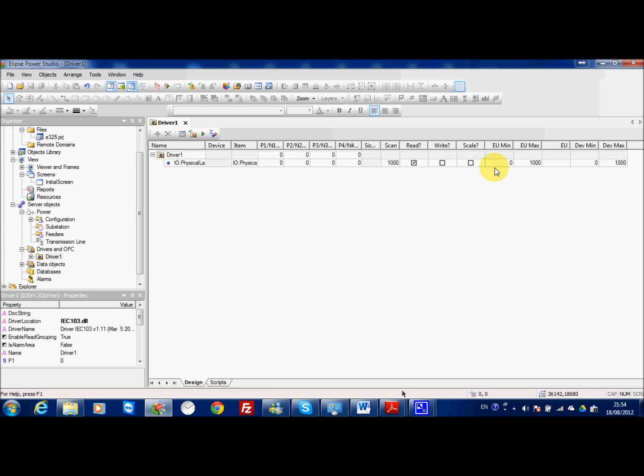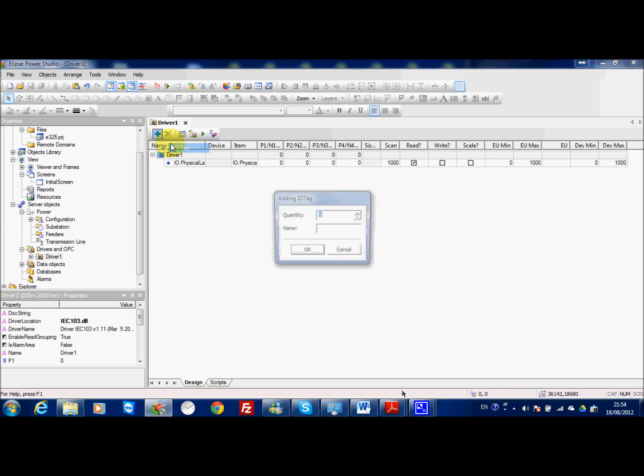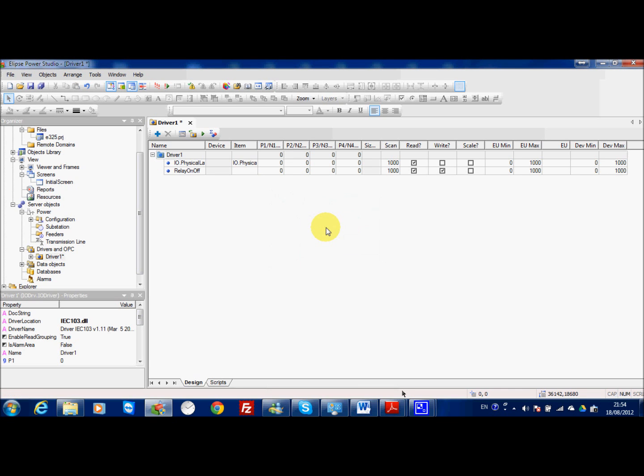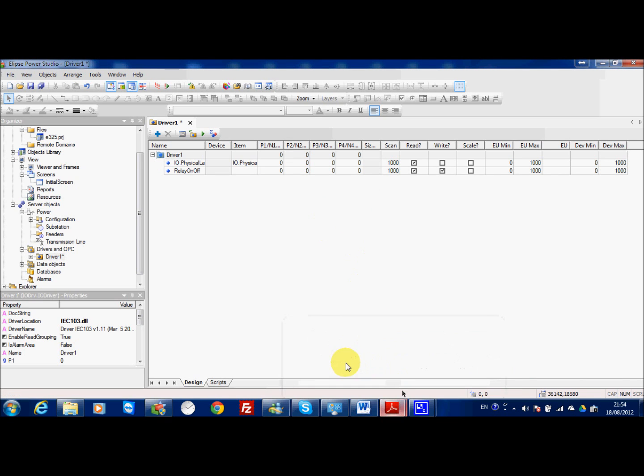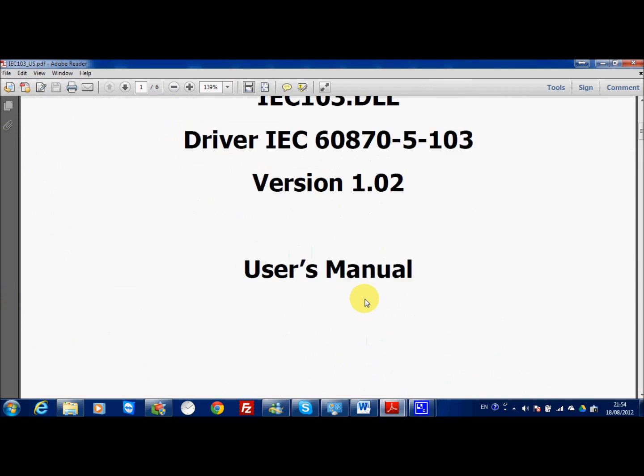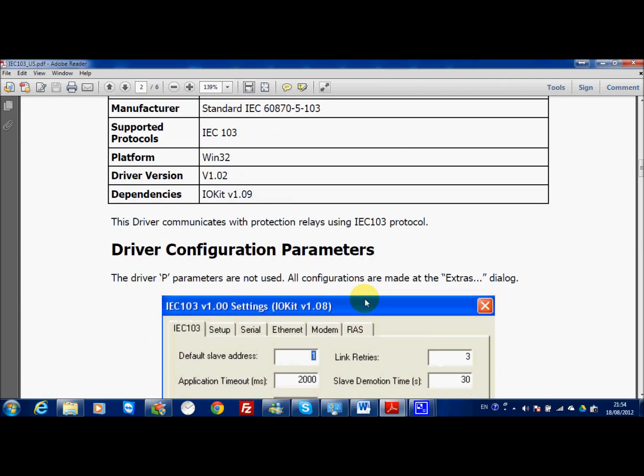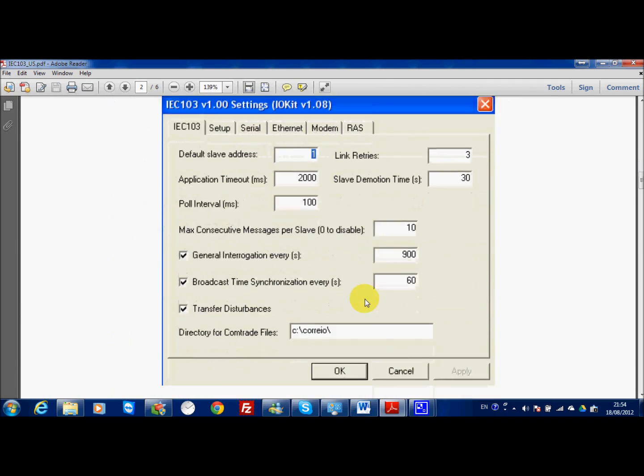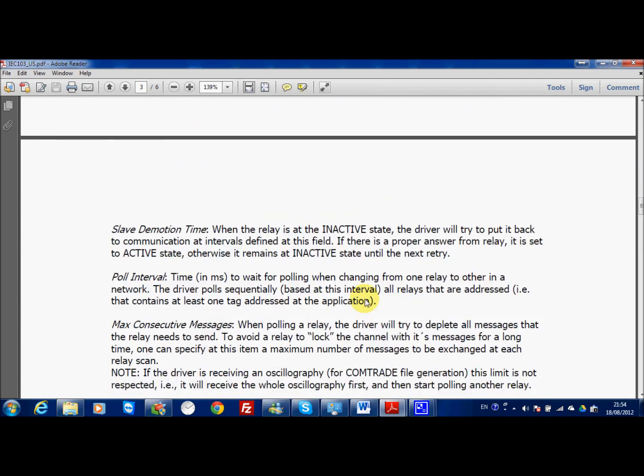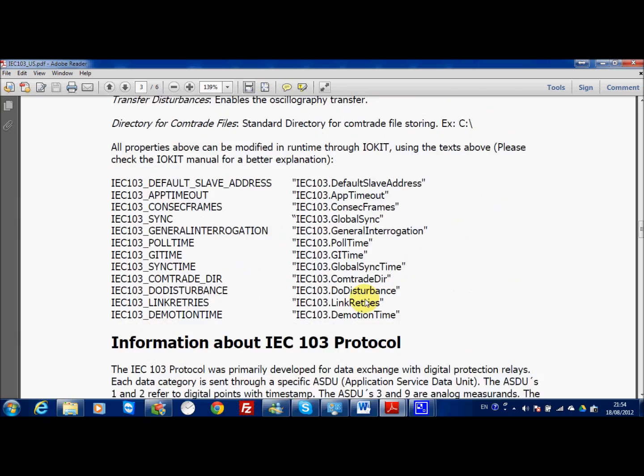In my case here I can start to build my driver. The first important tag you need to implement for the IEC-103 is the relay on-off. The relay on-off is one tag which you need to set to 1 if you want to start communicating with the device.